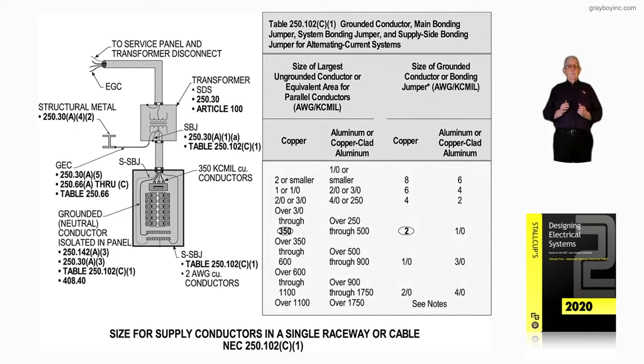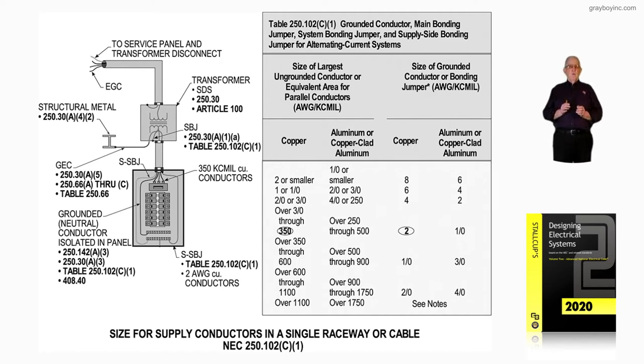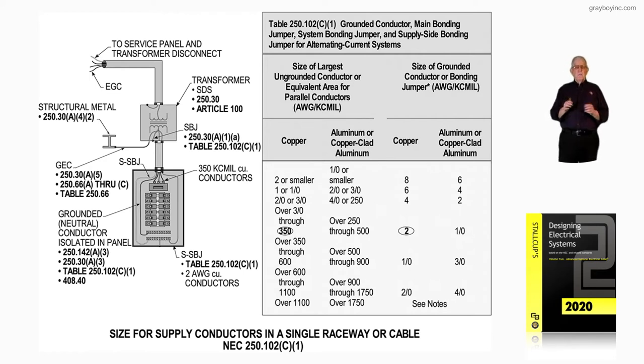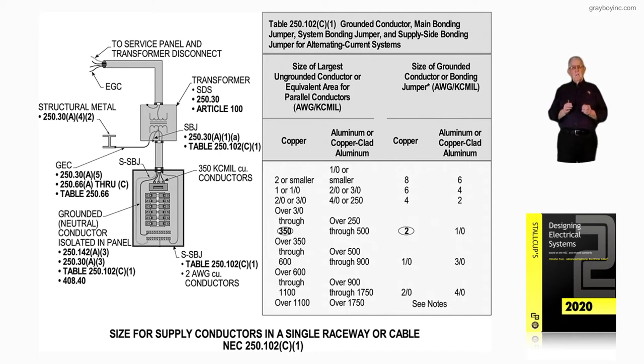Let's take a look at the service. Notice the service equipment at the very top talks about the service panel and service disconnect. We have a transformer that's a separately derived system, but it wouldn't make any difference — it could be a transformer located outside, like a utility or customer-owned transformer in accordance with 250.24A. But here we're talking about 250.30 and the definition of a separately derived system in Article 100.